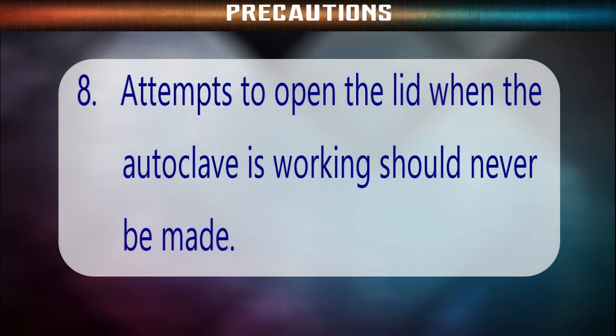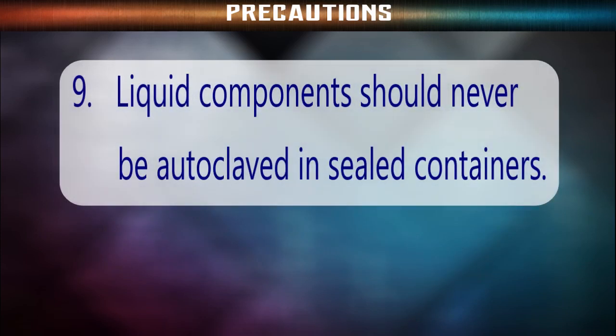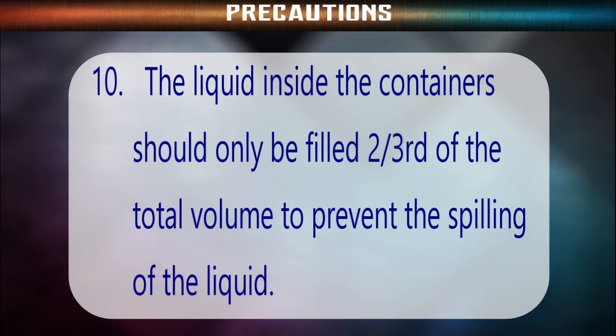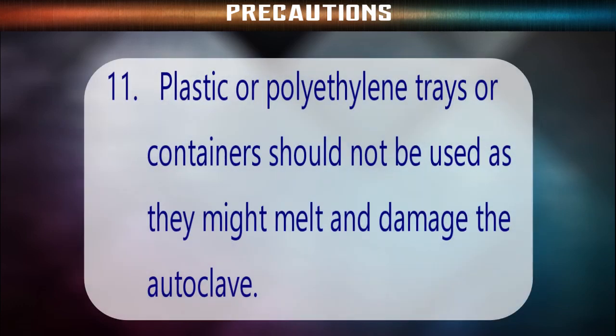An attempt to open the lid when the autoclave is working should never be made. Liquid components should never be autoclaved in a sealed container. The liquids inside the container should only be filled 2/3 of the total volume to prevent the spilling of the liquid. Plastic or polyethylene trays or containers should not be used as they might melt and damage the autoclave.